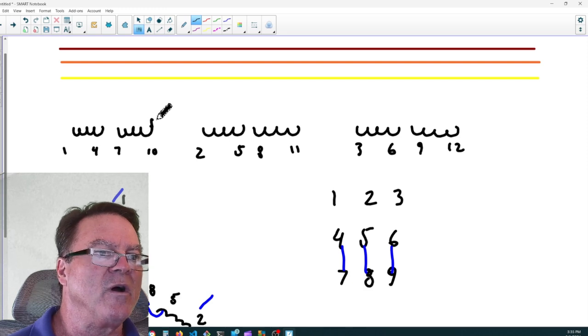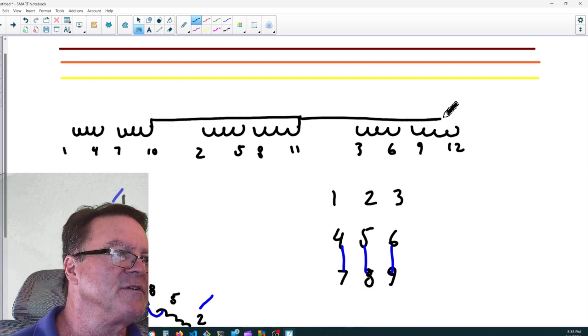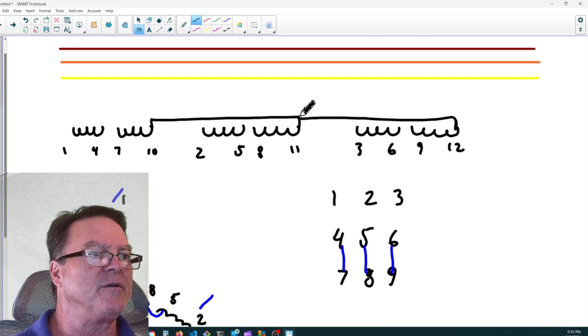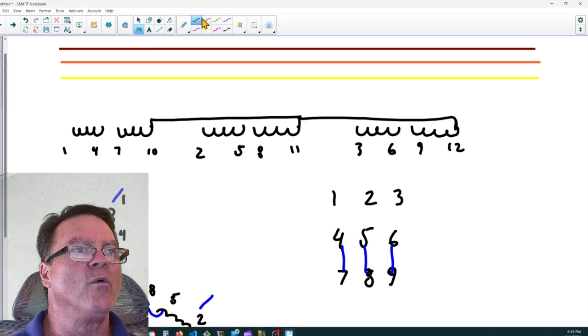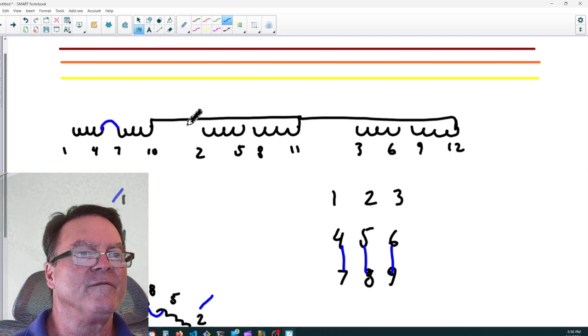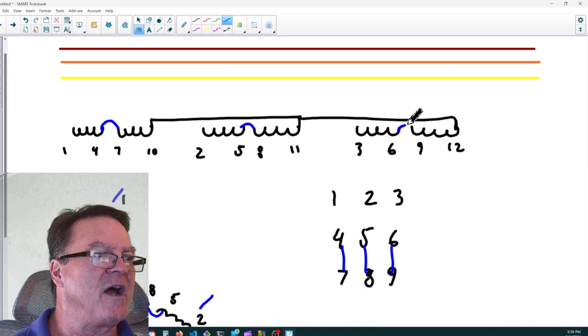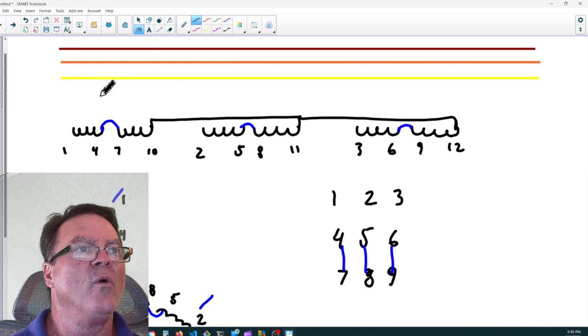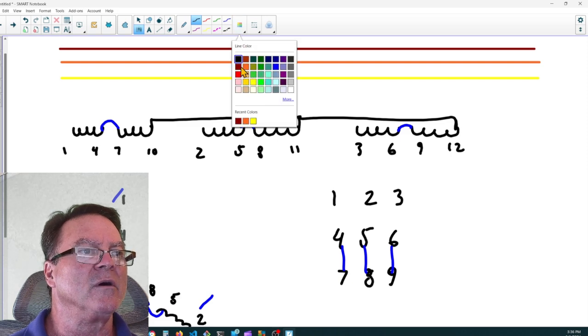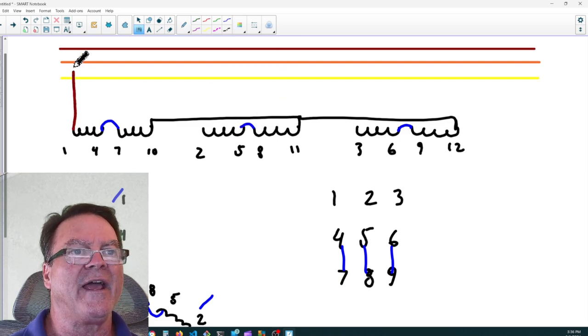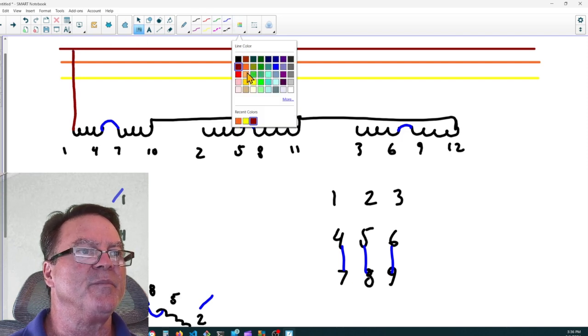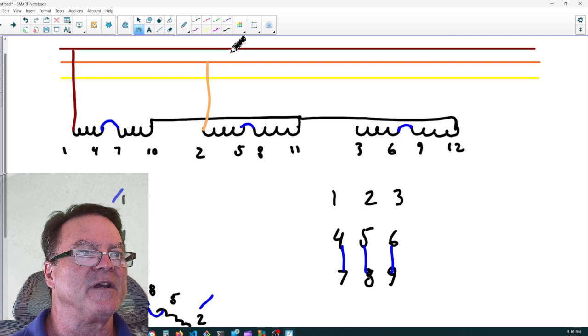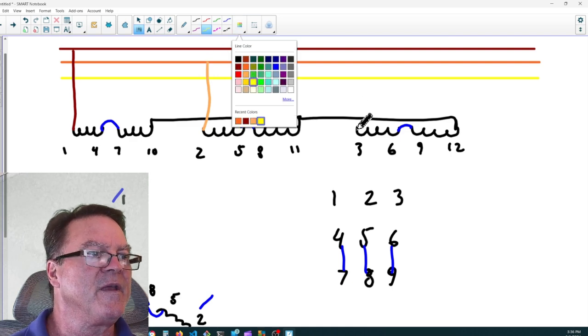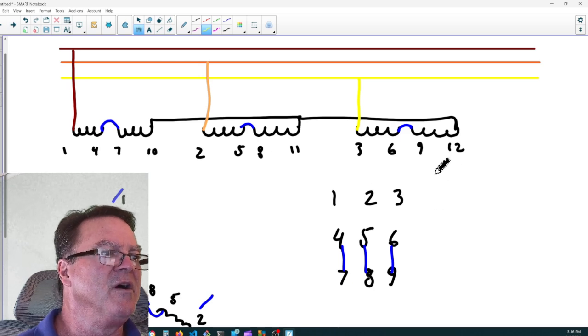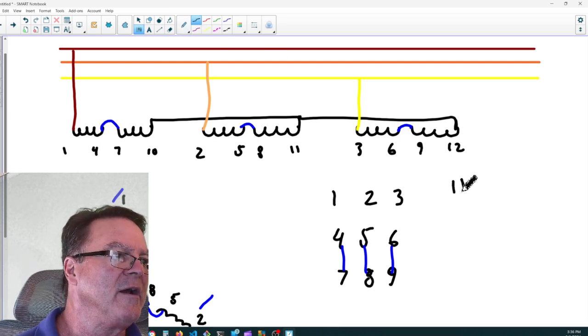So 10, 11, and 12 have already been hooked together. There, those are hooked together. And what we'll do is we'll take 4 to 7, 5 to 8, 6 to 9, and 1, 2, and 3 are going to be our leads out. So I'll take 1 to A phase, and I'll take 2 to B phase, and I'll take 3 to C phase. And now this motor's hooked up for high voltage Y. High Y.